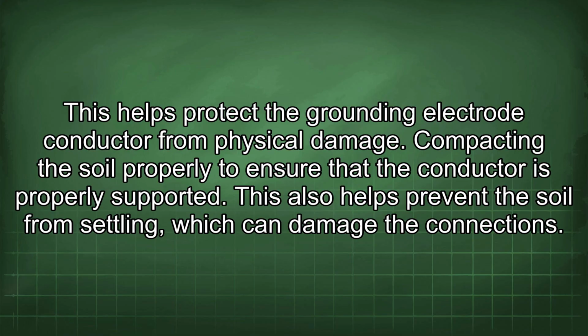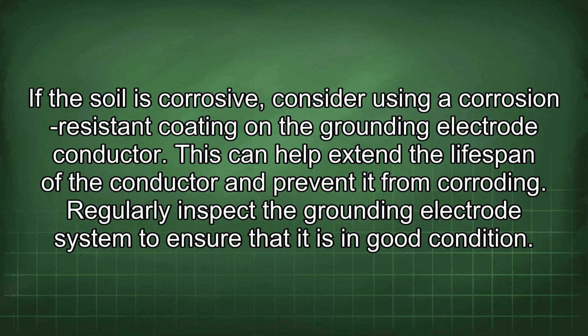Compact the soil properly to ensure that the conductor is properly supported. This also helps prevent the soil from settling, which can damage the connections. If the soil is corrosive, consider using a corrosion-resistant coating on the grounding electrode conductor. This can help extend the lifespan of the conductor and prevent it from corroding.